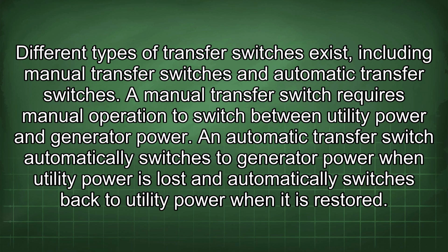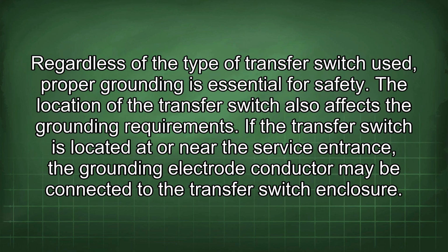An automatic transfer switch automatically switches to generator power when utility power is lost and automatically switches back to utility power when it is restored. Regardless of the type of transfer switch used, proper grounding is essential for safety. The location of the transfer switch also affects the grounding requirements.